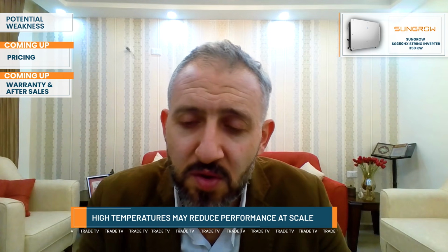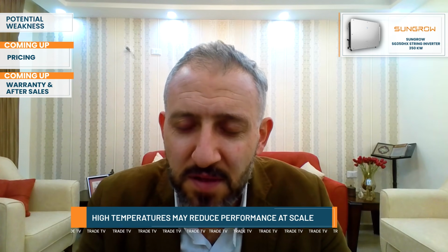The weakness for me is that sometimes at high temperature the VAR curve could give a lower performance than others. It's not very measurable, but at a certain level of megawatts, if you go to 100 or 200 megawatts, sometimes you will measure it.